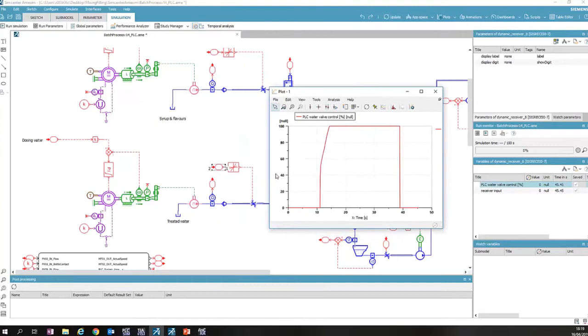I know that the flow in my dosing system, which I can also plot here, is closely linked to the speed of the pump. In this case we have a centrifugal pump moved by this motor, with a fixed speed configured, currently set to 2000. Probably if I increase this, I will be able to meet the flow requirements.